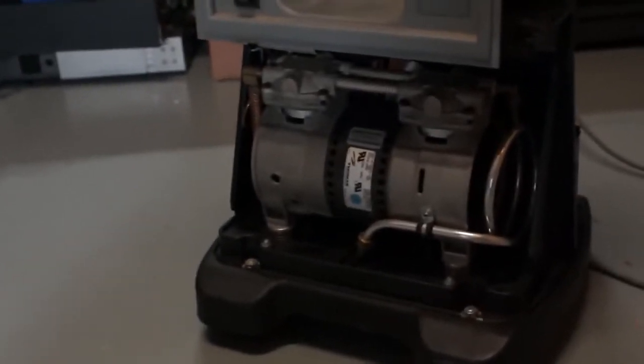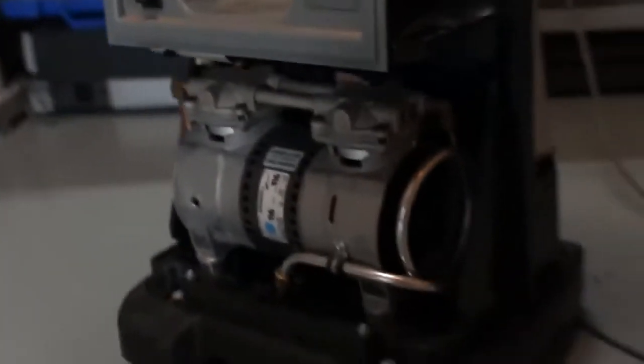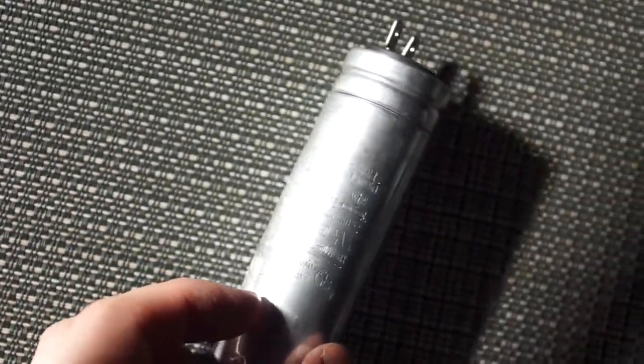That looks like all that's wrong with it. I oiled the motor and compressors, and I now think it's just the starter capacitor that's failed. That's up in there. And I do have replacements of those, so that'll be an easy fix. So here's the failed capacitor. You can get a macro shot of this. It's hard to read here. I can read it to you. It says at 60 hertz, it's 500 volt, 15 microfarad, which I definitely have capacitors this size. I just got to go find them.